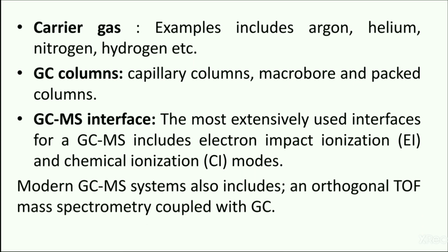Modern GCMS systems also include an orthogonal time-of-flight mass spectrometer coupled with GC. In these instruments, orthogonal acceleration combined with collisional ion cooling allows separation of the ion production in the ion source and accurate mass analysis. By using this technique, high resolution can be achieved for ions produced in matrix-associated laser desorption ionization or electrospray ionization sources.